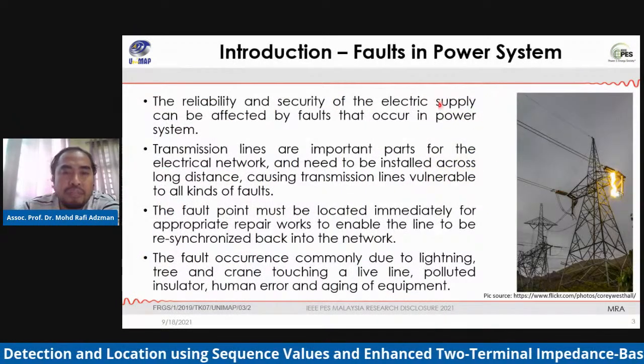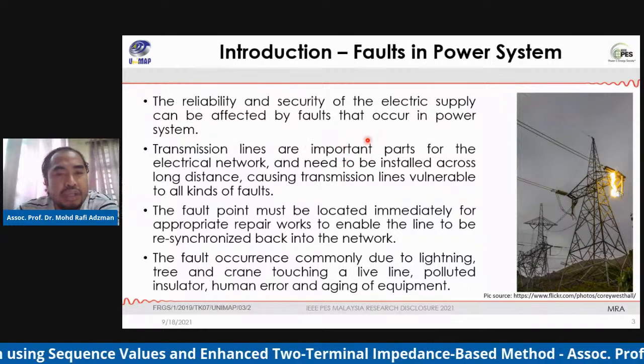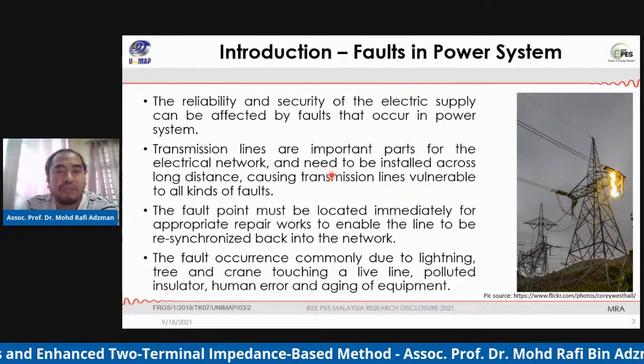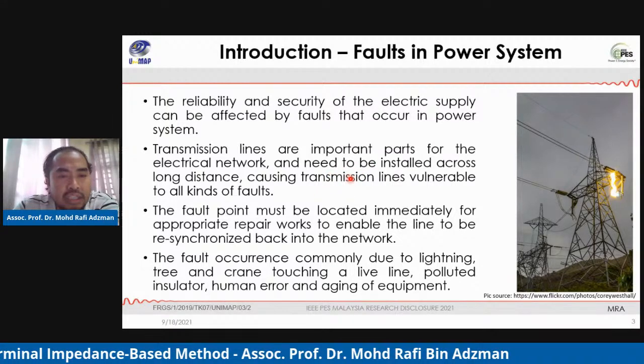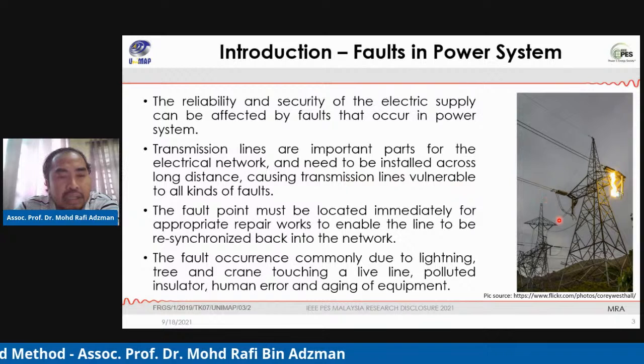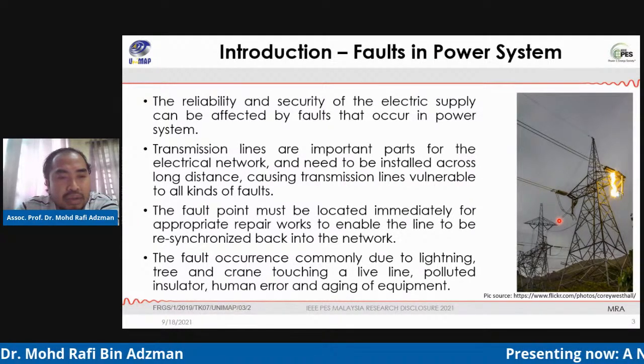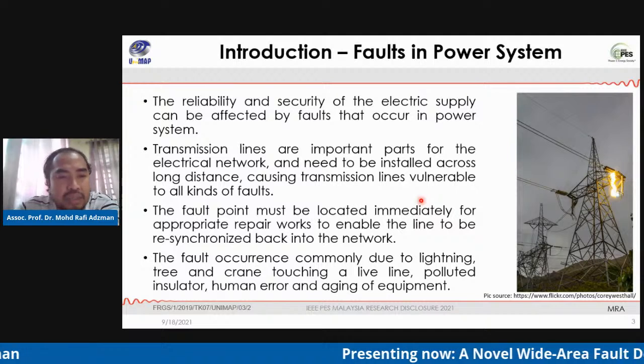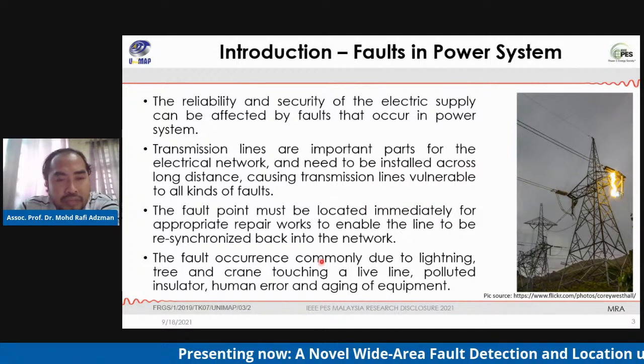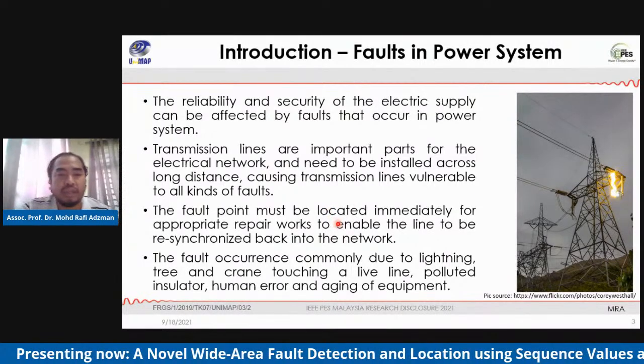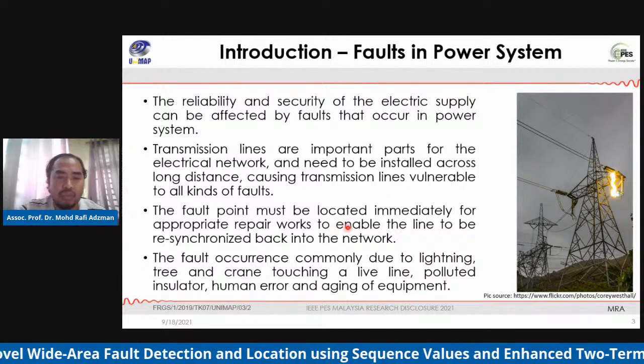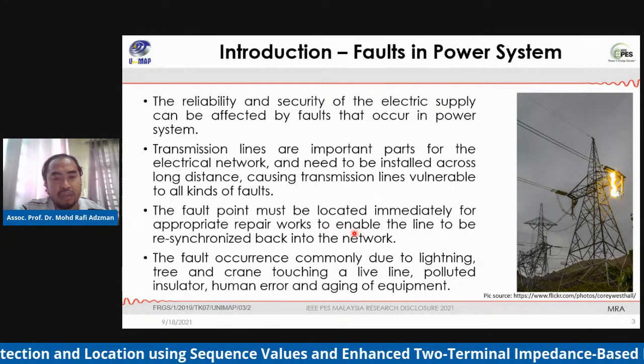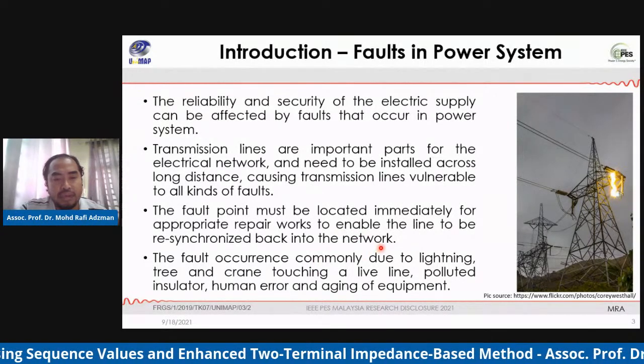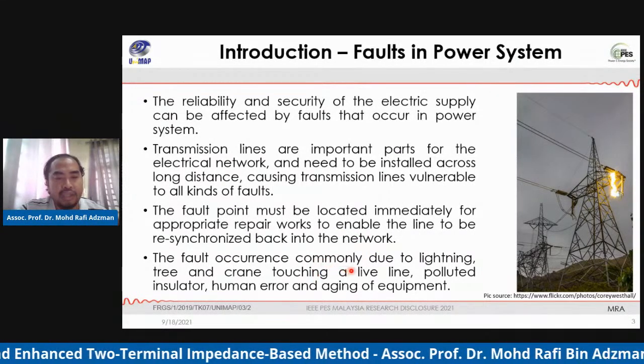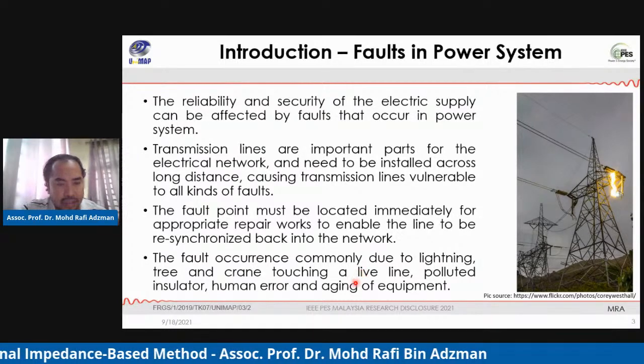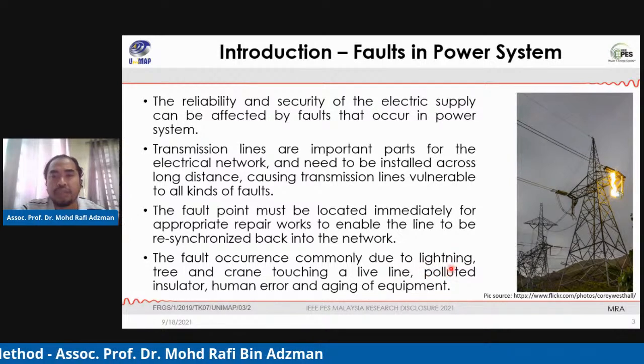Introduction to faults in power system. The reliability and the security of the electric power supply can be affected by the faults that occur in power system. The transmission lines are important parts of the electrical network, and they need to be installed across a long distance, causing transmission lines to be vulnerable to all kinds of faults. When a fault occurs, we need to locate the fault immediately in order to do repair works and to resynchronize back into the network. Faults may be due to lightning, a tree, a crane touching a live line, polluted insulators, human error, and aging of the equipment.